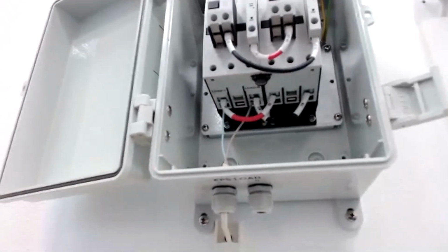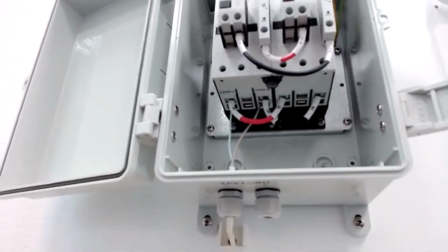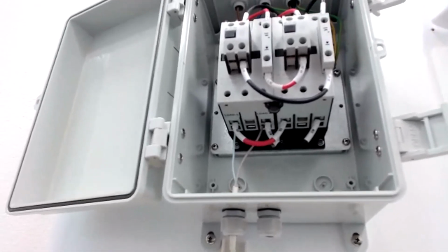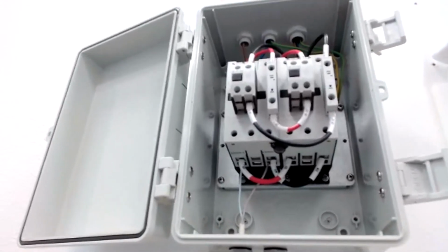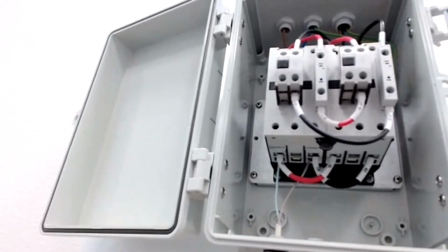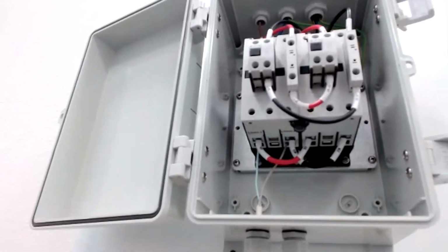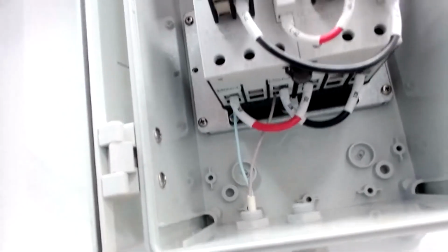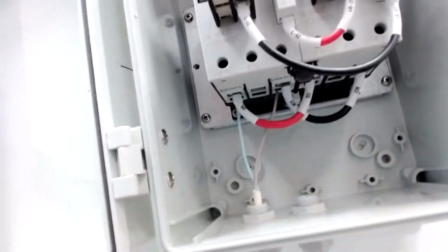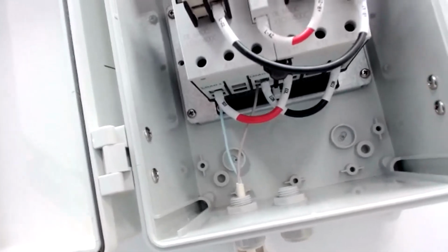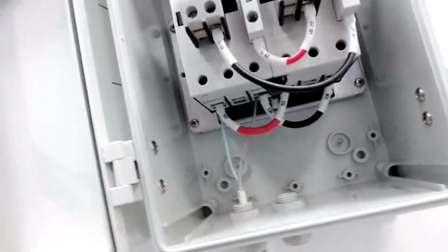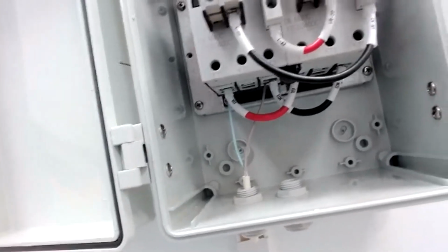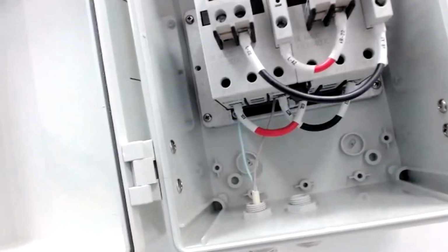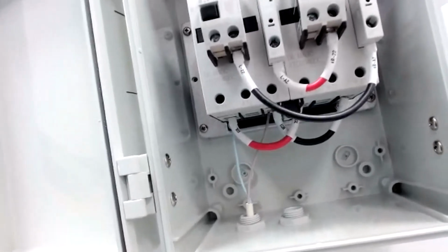You can build an extra circuit for the things you want to power, like servers or PCs or anything that has to run all the time. Or you can connect the whole house to this, but you have to know we have a maximum output of 14.5 amps at 6,000 watts. If you have a demand bigger than 14.5 amps, which is really high by the way, the inverter will shut down for safety reasons. Nothing will break or be damaged, it will just shut down.